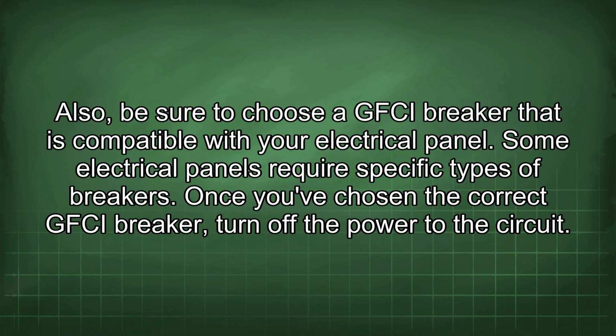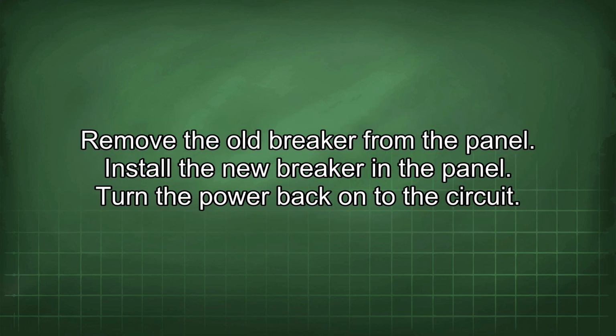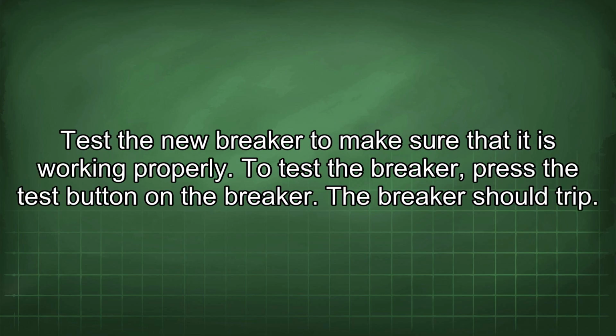Once you've chosen the correct GFCI breaker, turn off the power to the circuit. Remove the old breaker from the panel. Install the new breaker in the panel. Turn the power back onto the circuit. Test the new breaker to make sure that it is working properly.